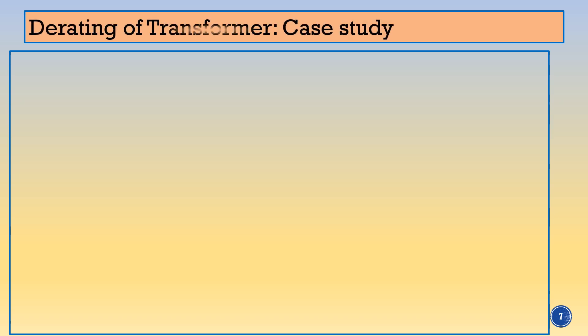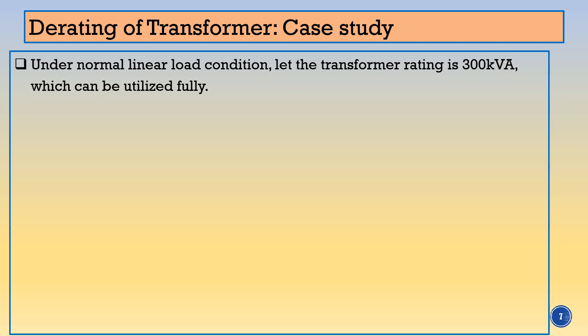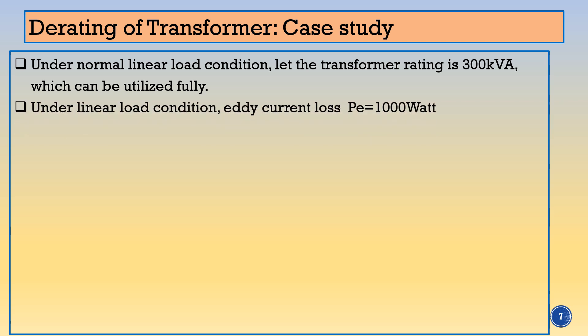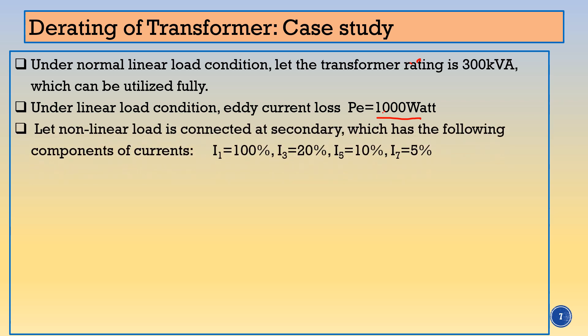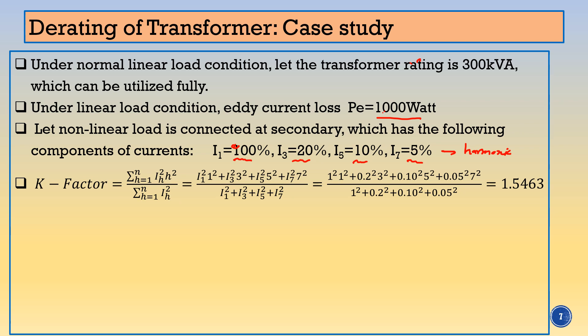Let us study this with a case study. Under normal load condition, let the transformer rating be 300 kVA, which can be utilized fully under the linear load condition. Let eddy current losses be 1000 W. Let a nonlinear load be connected at the receiving end. The fundamental component of the current is 100%, third harmonic is 20%, fifth harmonic is 10%, and seventh harmonic is 5%. You can get this data from any harmonic analyzer if you connect it across the nonlinear load.